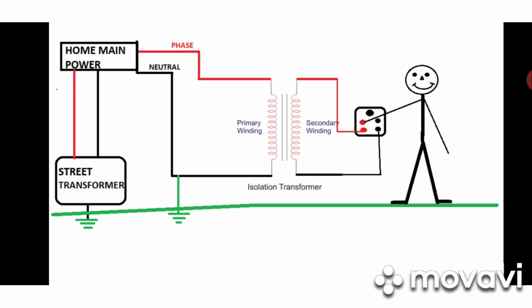If a man touches the red phase wire now, he won't feel any shock because there is no earth connection in the secondary part. In the normal transformer, the neutral is connected to earth, but in the isolation transformer's secondary winding, there is no neutral and no connection between earth and the secondary winding. So the electron flow is not completed, and he won't get any shock.